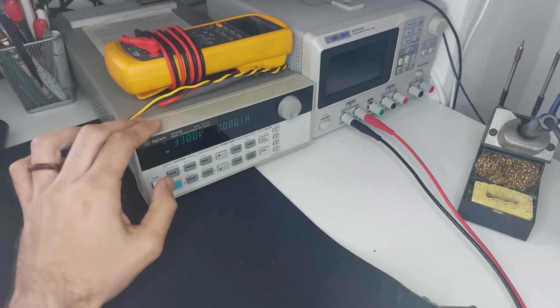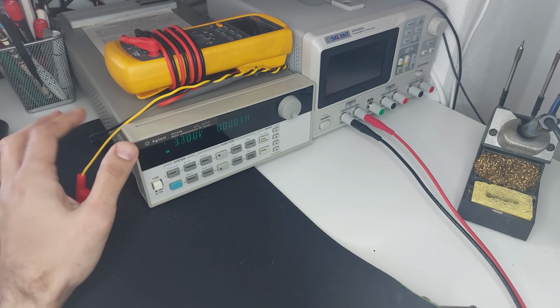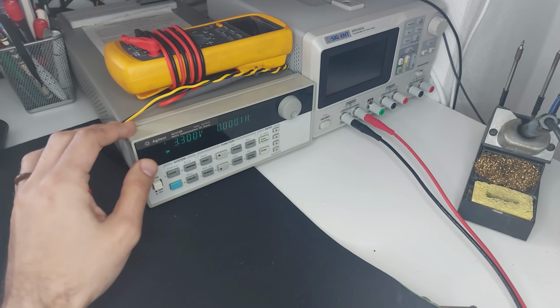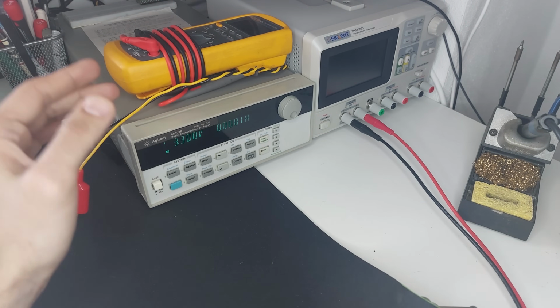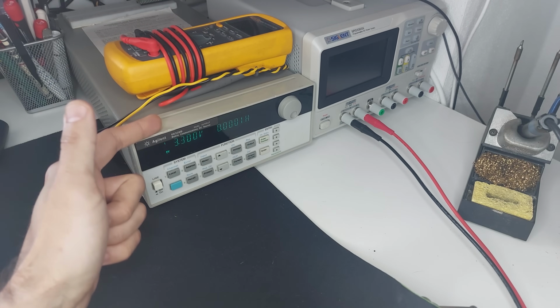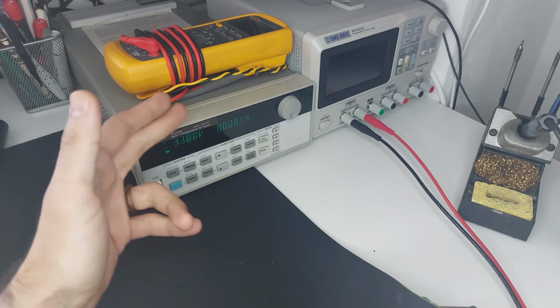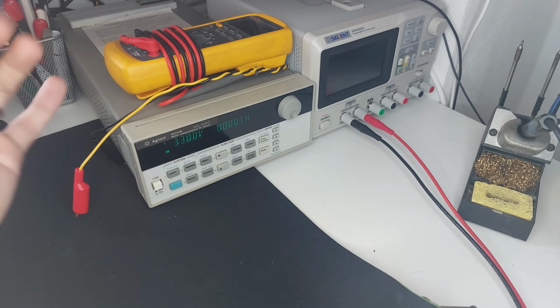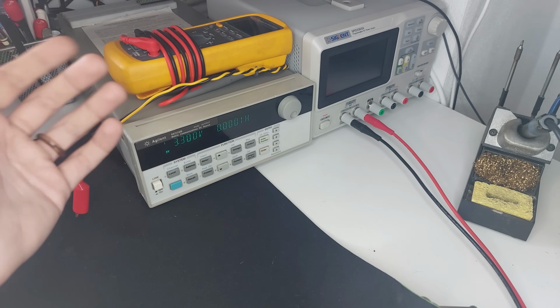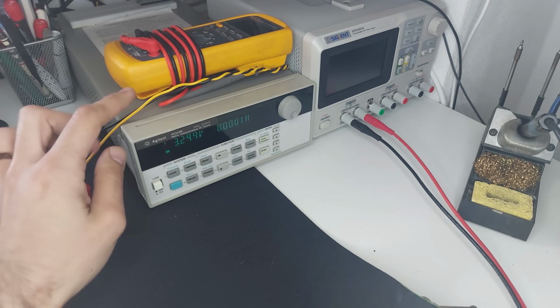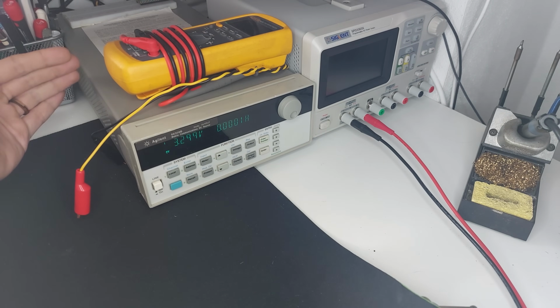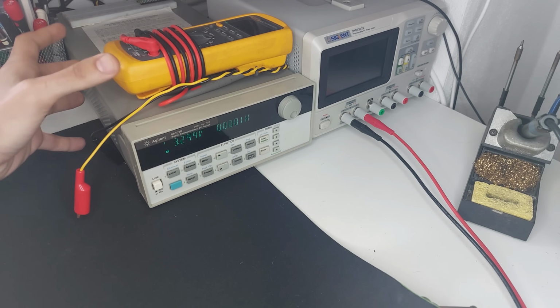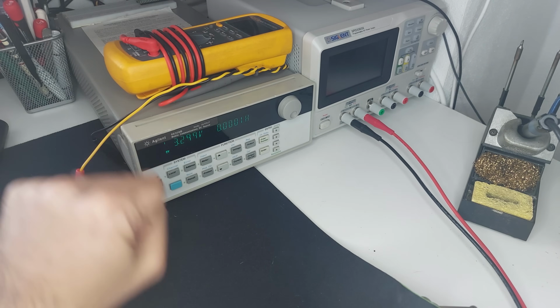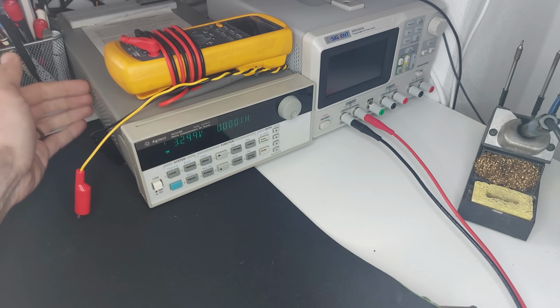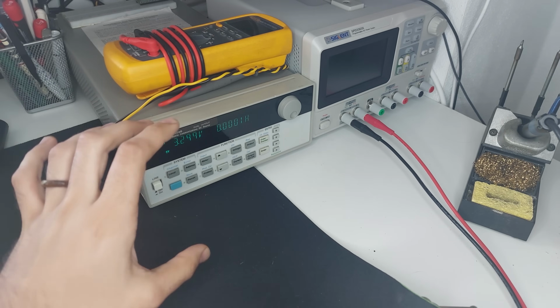So the transformer in this unit, which is 40 watts, and the fan, the transformer is bigger than in the Agilent. It's got two channels, a 15 volt 3 amp channel and a 12 volt 1 amp channel. So 40-ish watts, 50-ish watts, something like that. This transformer goes up to here in the power supply. It spans almost the entire width of the instrument. It's massive. I'll show you the insides a bit later.